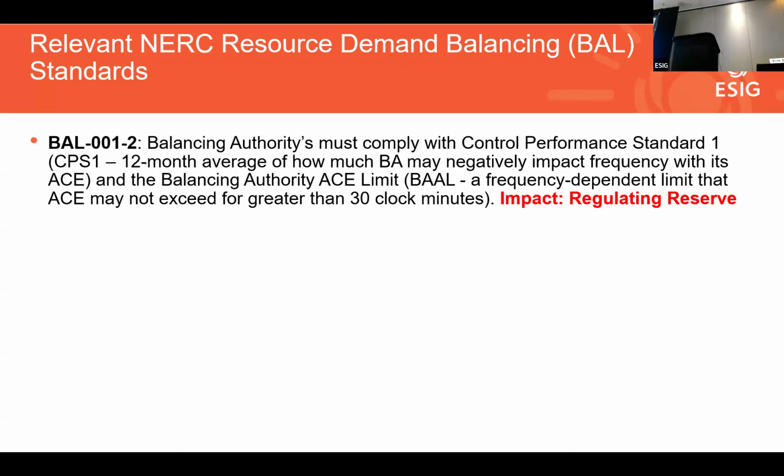So for regulating reserve, there is not a NERC standard that says a balancing authority has to have a minimum amount of regulating reserve. That's really up to each balancing authority, or an ISO/RTO if they have that type of a reserve product. But there is a performance standard that says if you have this much imbalance, you will be penalized through these NERC standards.